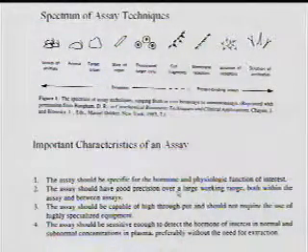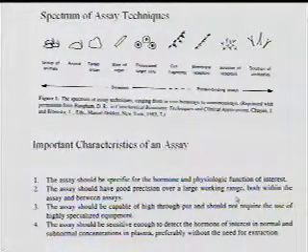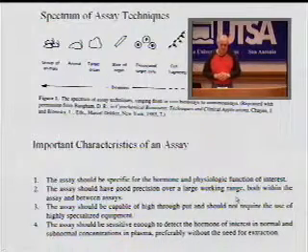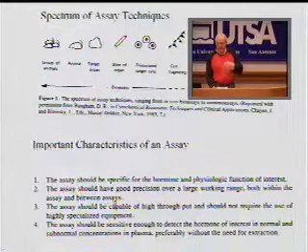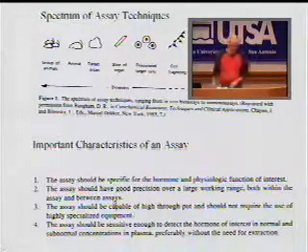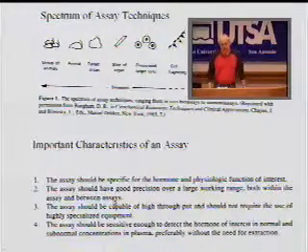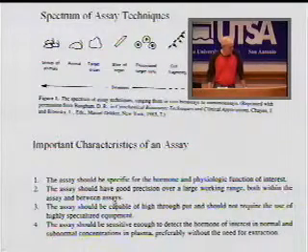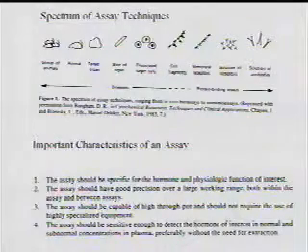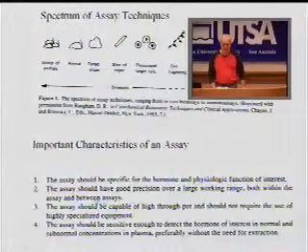And so you want a low variance not only within each measurement that you take, each time you run the assay, you want to be sure that when you run it from day to day or morning to afternoon, that you have controlled variance, or the same degree of variance, from assay to assay. So within an assay, this is called intra-assay variation, and there are methods to control that. And between the assays is the inter-assay variation.